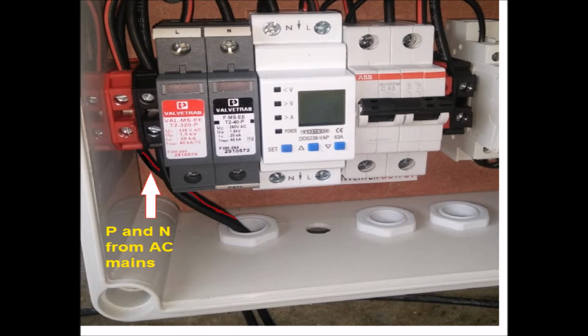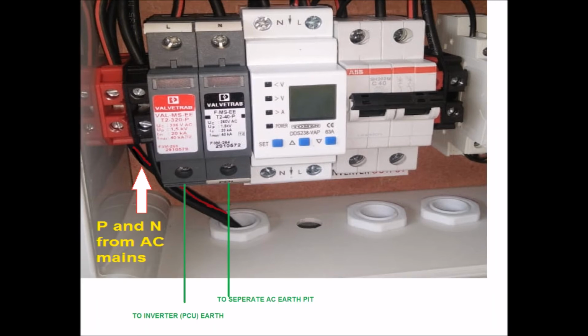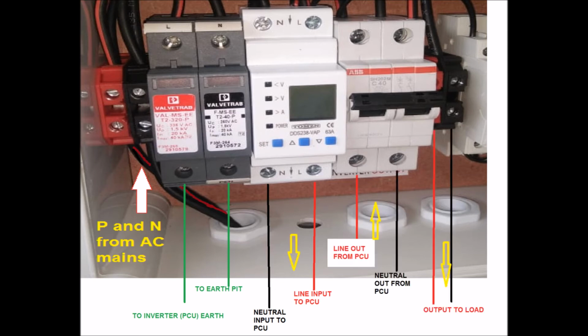Wires from mains inputs are connected to the terminals on the left side. SPD1 is connected to the earthing of inverter. SPD2 is connected to the earthing pit. Input to the inverter is taken from the voltage controller. Output from PCU goes to MCB and output to load is taken from the terminals on the right.